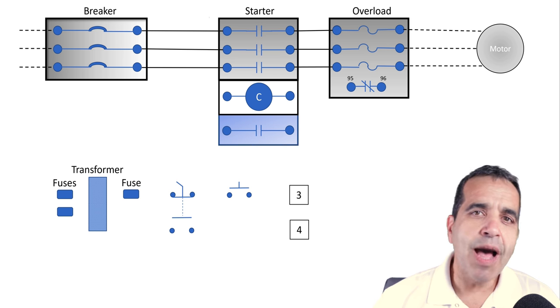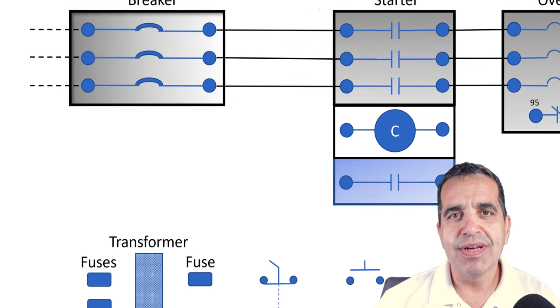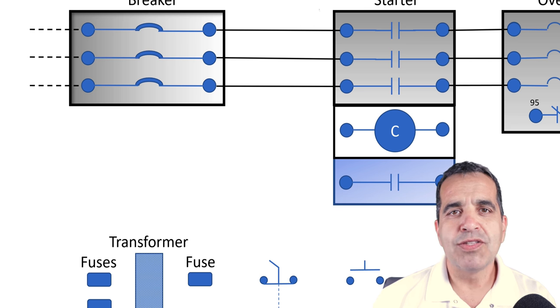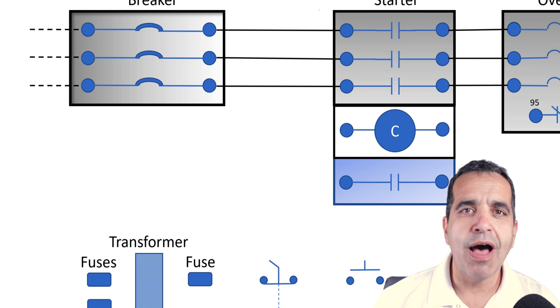Off the top of the starter, there is a tap on line one and on line two. Two black wires are tapped to those lines and they're feeding two fuses that are mounted to the top of our control transformer.